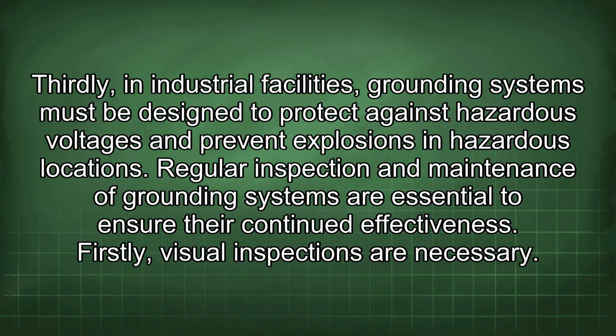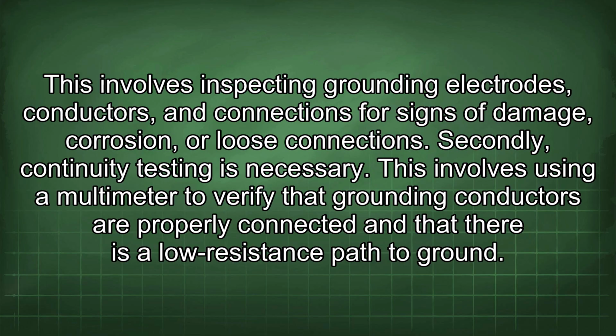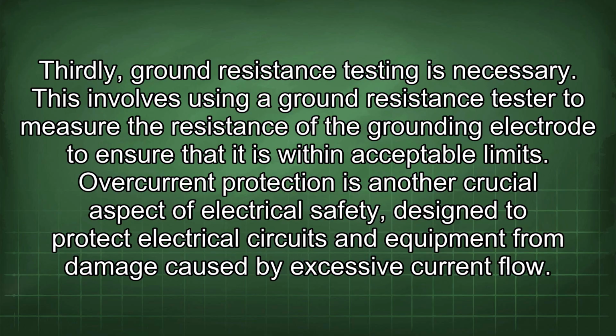Regular inspection and maintenance of grounding systems are essential to ensure their continued effectiveness. Firstly, visual inspections are necessary. This involves inspecting grounding electrodes, conductors, and connections for signs of damage, corrosion, or loose connections. Secondly, continuity testing is necessary. This involves using a multimeter to verify that grounding conductors are properly connected and that there is a low resistance path to ground. Thirdly, ground resistance testing is necessary. This involves using a ground resistance tester to measure the resistance of the grounding electrode to ensure that it is within acceptable limits.